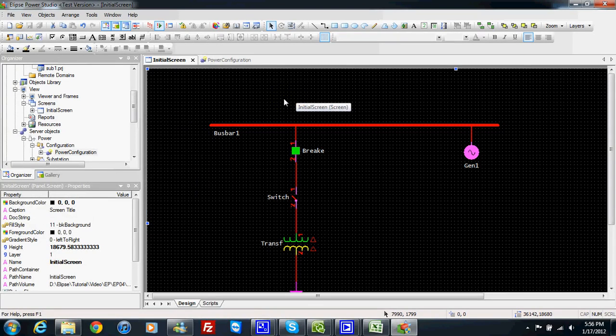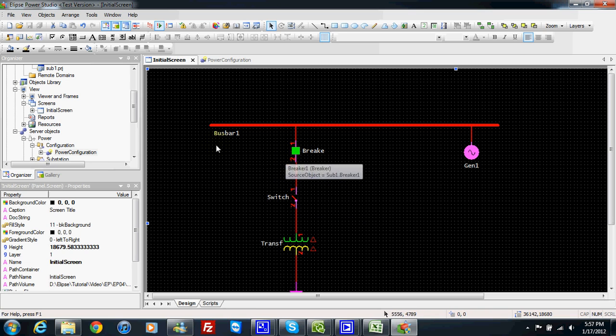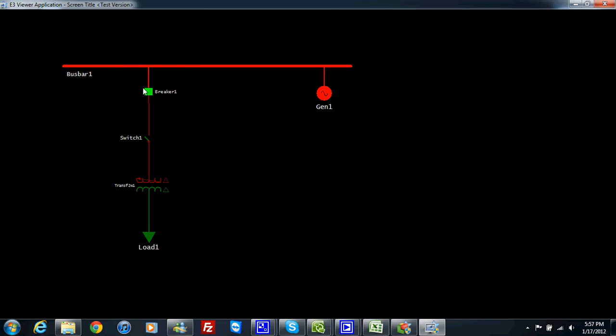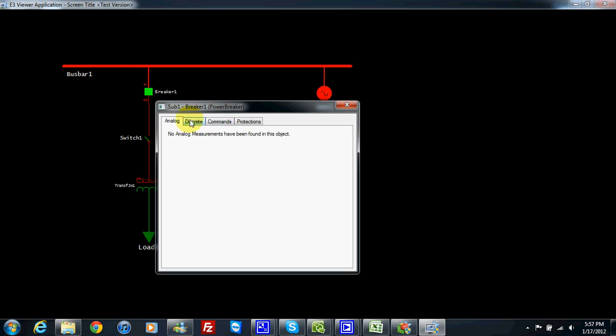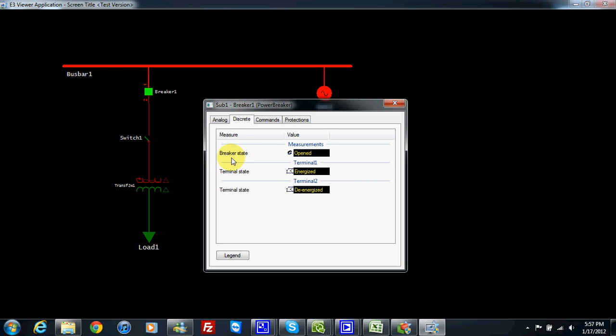In this video I will show you how we can add a command to a breaker or to a switch. To add a command we need to understand how the system works. Right now I have breaker one, and in measurement in command I have nothing listed. I have no commands to breaker one, but here I can have the breaker state — this is the breaker position, and the current value is open.